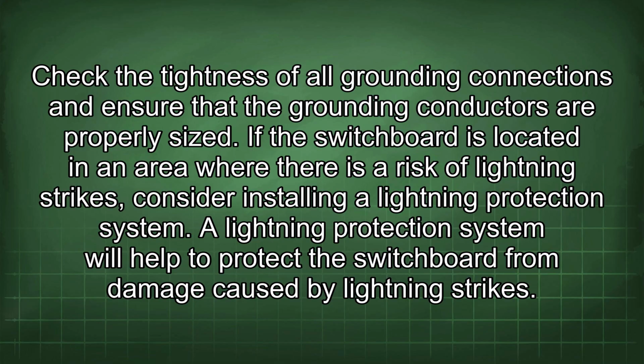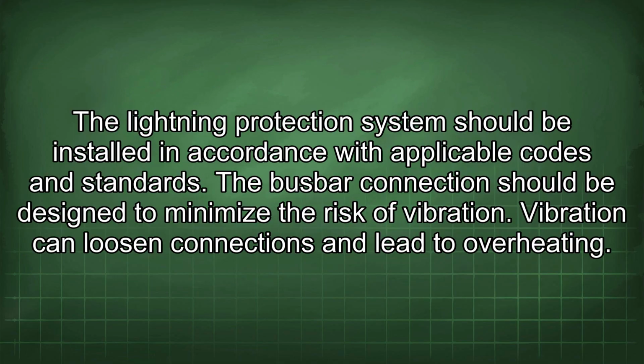If the switchboard is located in an area where there is a risk of lightning strikes, consider installing a lightning protection system. A lightning protection system will help to protect the switchboard from damage caused by lightning strikes. The lightning protection system should be installed in accordance with applicable codes and standards.